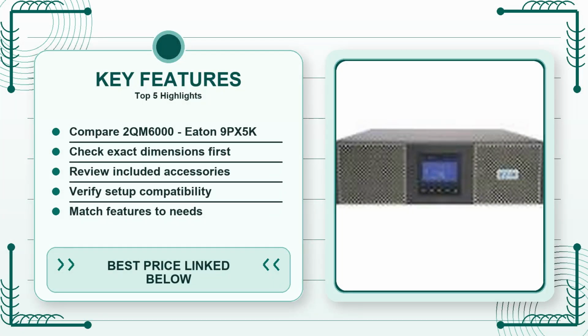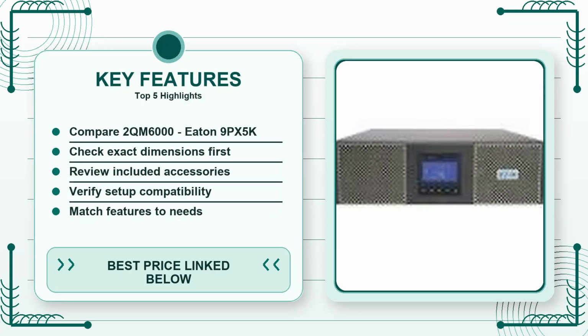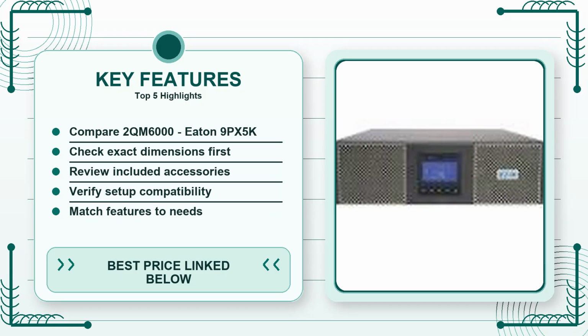On the flip side, if you're a laptop user who only needs a few minutes of backup for a single device, the 9PX5K is overkill. The unit is sizable, weighing close to 70 kilograms, and requires a dedicated space and a proper grounding point. It's not something you'll want to tuck under a desk or move around often. For a home office with a single desktop and a couple of peripherals, a 1 kVA or even a 1.5 kVA UPS would likely be sufficient and more cost-effective.